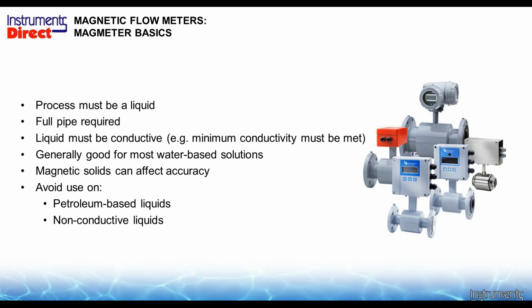So things that are not conductive are not going to work, such as any petroleum or hydrocarbon-based applications, or some other interesting things like deionized water. Deionized water is water with nothing in it. They take all the minerals out of the water, and the water is not even conductive at that point. So DI water and some RO water applications have very low to no conductivity. So those are really the only gotchas. Anything else that's really water-based, for the most part, is generally a good application.